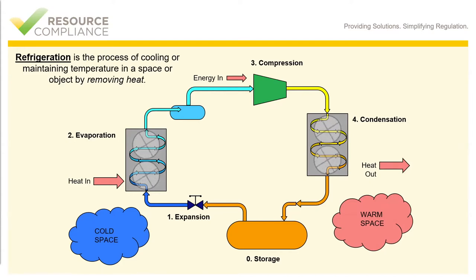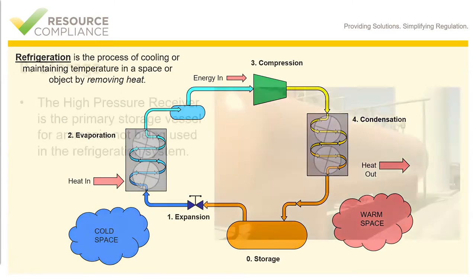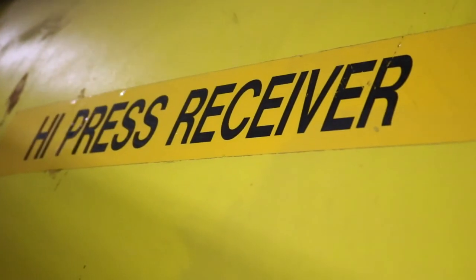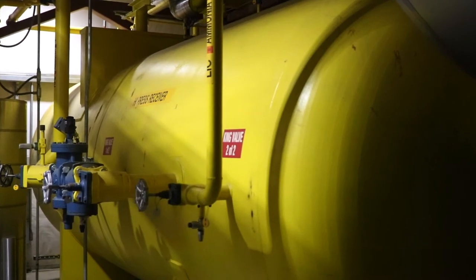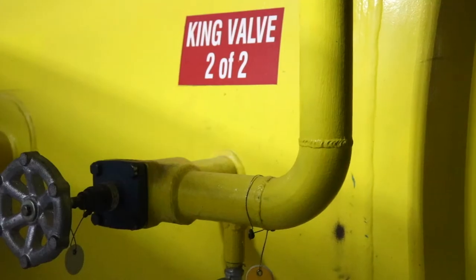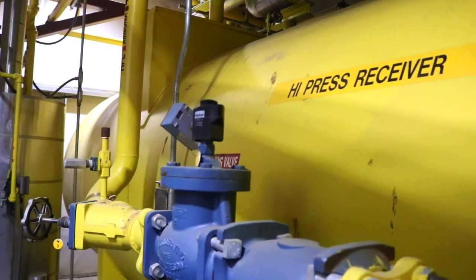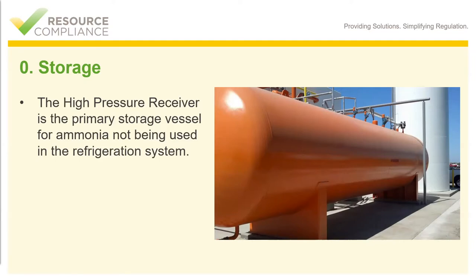In the real world of cold storage, warehouses, and wineries, a storage vessel really is a necessary component. The high pressure receiver, commonly referred to as the HPR, is the primary storage vessel for ammonia that is not being used out in the system. It's important to note that this vessel, or any pressure vessel, should never contain more than 85 percent of its total capacity. The reason for this is vapor expansion — as ambient temperatures rise, the high pressure liquid ammonia inside the vessel may expand, causing an increase in pressure.